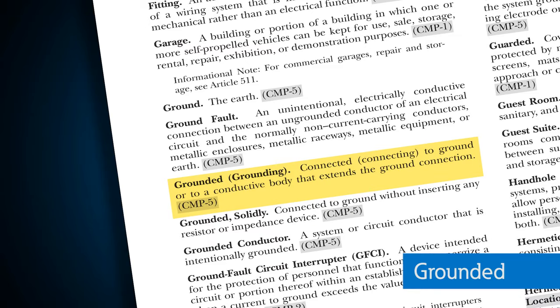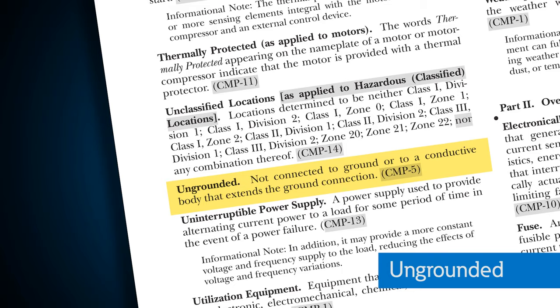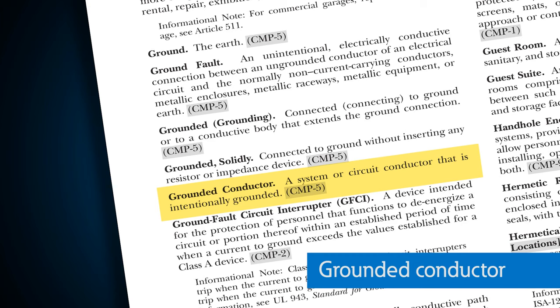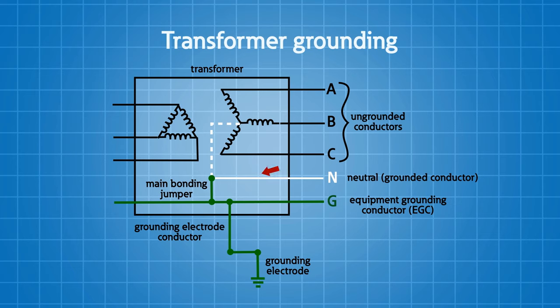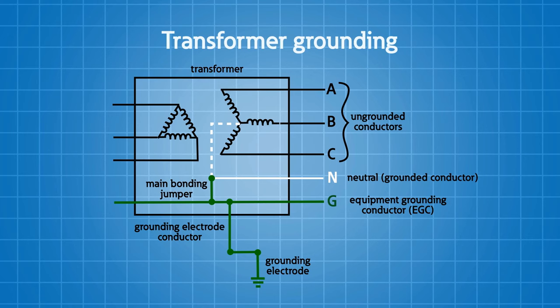'Grounded' means we are connected to the earth or to some body that extends that earth connection. 'Ungrounded' is just the opposite — not connected to ground or to a conductive body that extends that ground connection. The grounded conductor is the system or circuit conductor that is intentionally connected to the earth at one point; we usually refer to this as the neutral. Its counterpart, the ungrounded conductor, is a circuit conductor that is not intentionally connected to the earth — usually your phase conductors.